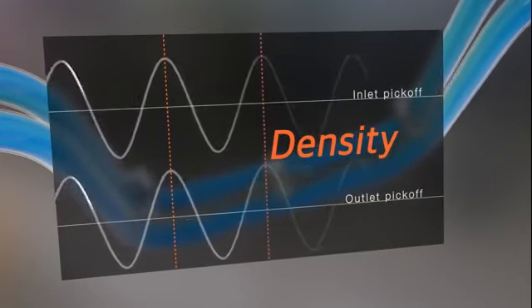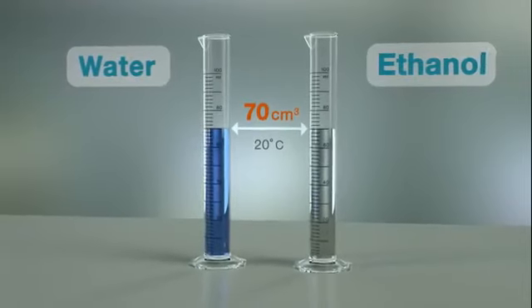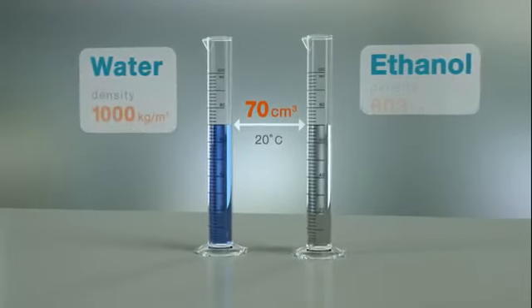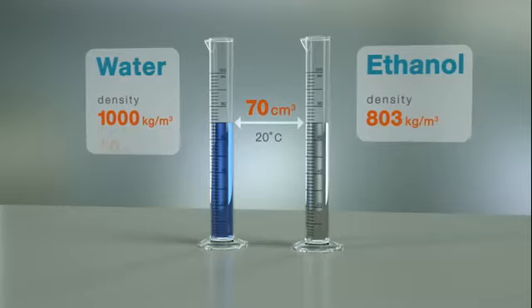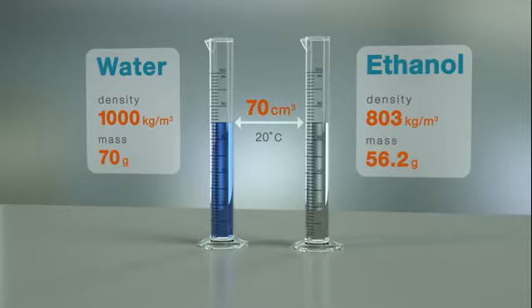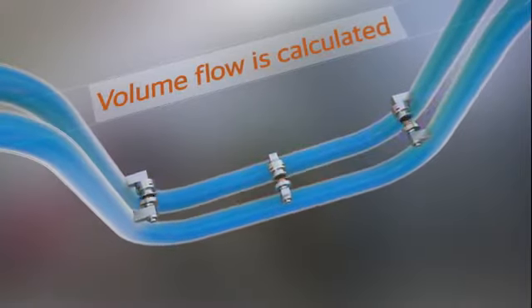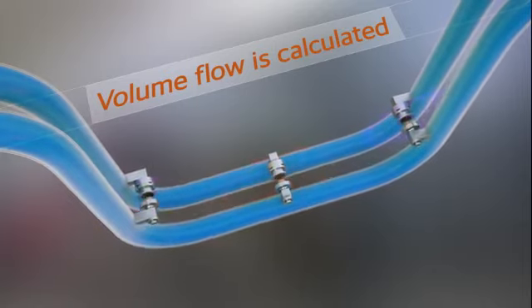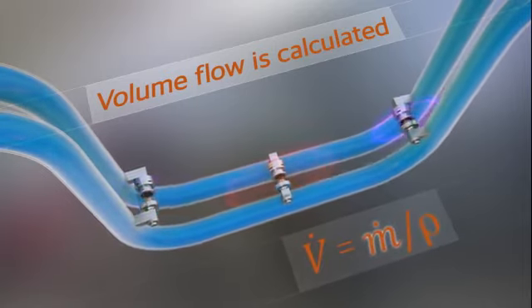Therefore, the mass and density of the fluid contained in the fixed volume of the flow tubes is the only variable affecting the frequency. Liquid volume flow is derived from the mass flow and density measurements already acquired. As in this example, fluids can have the same volume, but different densities and masses. The mass and density measurements allow the calculation of the volume flow.